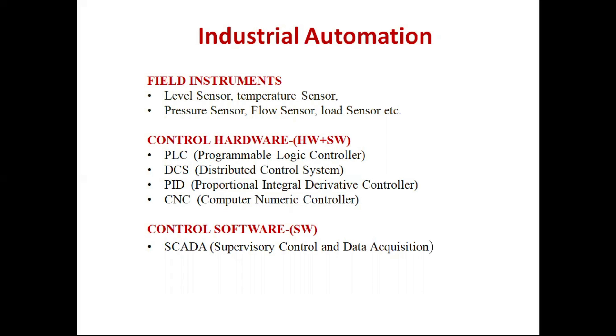These instruments act as the eyes of any process — they measure process parameters and give us feedback in the form of current or voltage, typically 4 to 20 milliampere or 0 to 10 volts. This signal then goes to the input of the PLC. The control hardware can be of different types like PLCs, DCS, PID controls, and CNC controls.